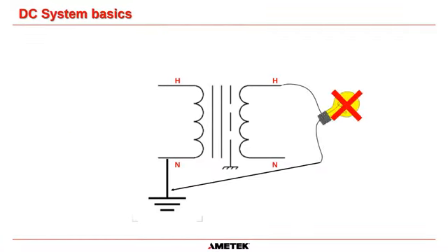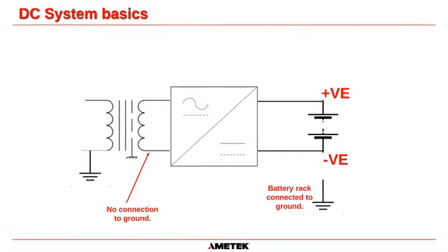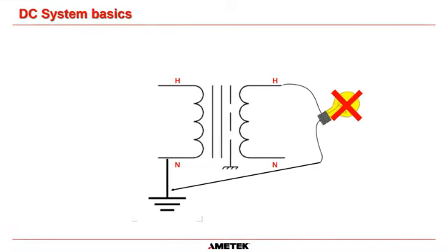But if we connect a lamp or light bulb between the hot on the secondary side of the transformer directly to a ground connection, there is no return path for that electricity to flow. So the lamp will not light. It's impossible. It cannot light, because there is no return path to that ground circuit because of the isolation between the two windings. And that's exactly the same for the neutral. Let me go back here. If you connected the lamp to the neutral and down to ground, the lamp would not light. There is no electricity flowing.